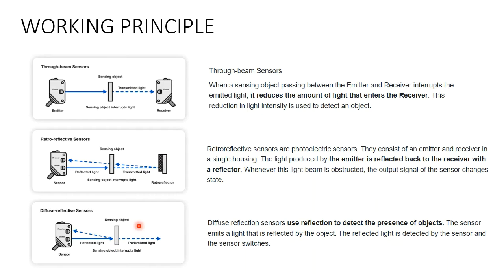Because the intensity of reflected light varies with object properties, the diffuse sensor can produce false alarms. Surrounding ambient light also contributes to errors in this sensor type, so it is not as reliable as the other two sensor types. These are the three basic types — let's now check out some application examples.